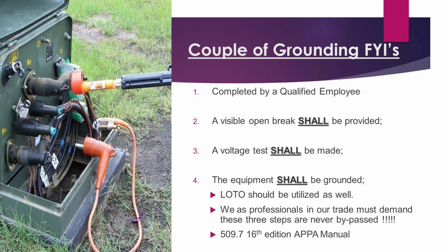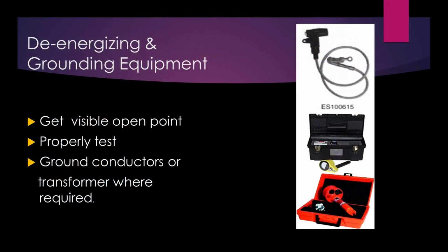Of course, when you're talking about grounding, you've got to have a visible opening point, test for voltage, and then install your equipment or grounds. You'd hate to try to put grounds on before you test, and just FYI, that probably wouldn't work out well. If you did do that, you'd probably only do it one time and never have to worry about it again. So get your visible open point, properly test it, and use your ground conductors or transformers when required.